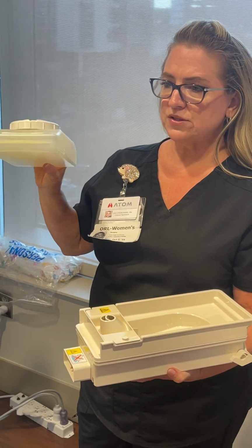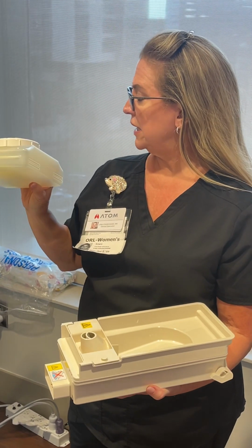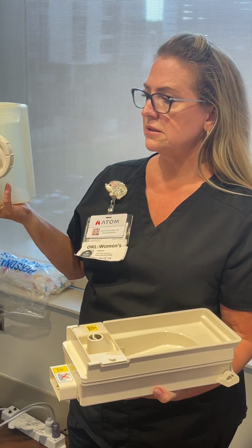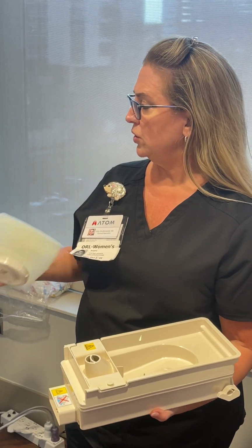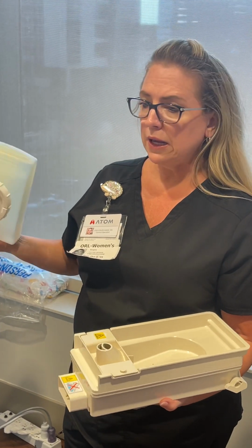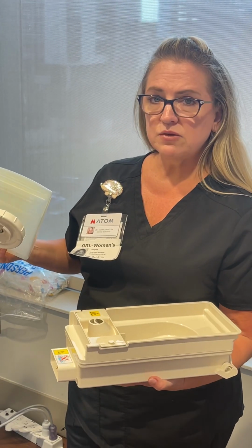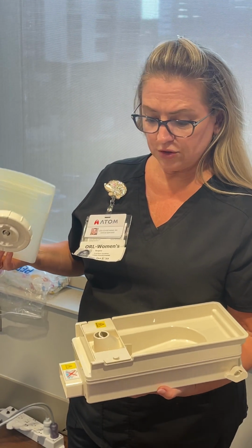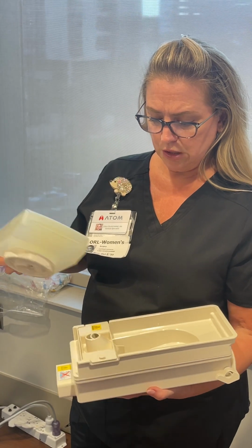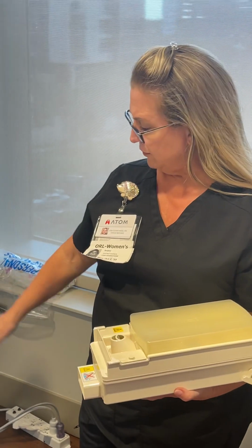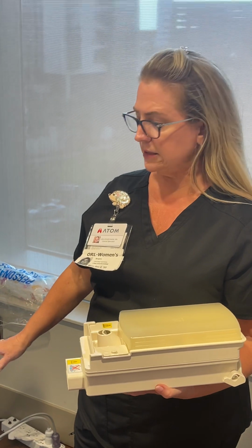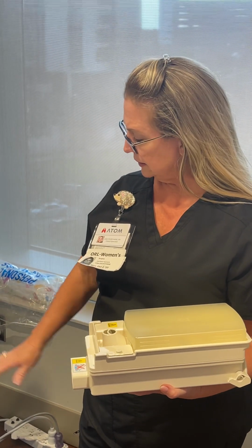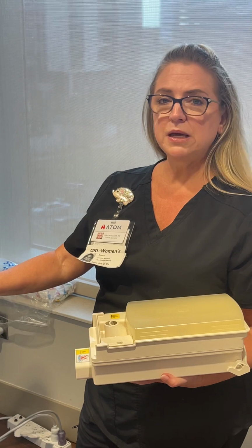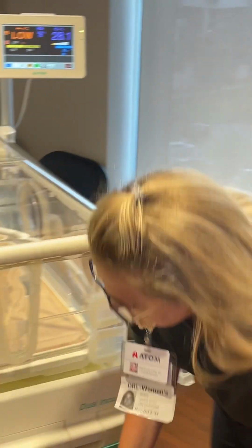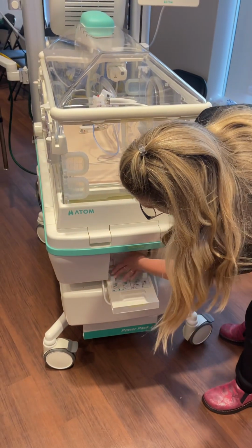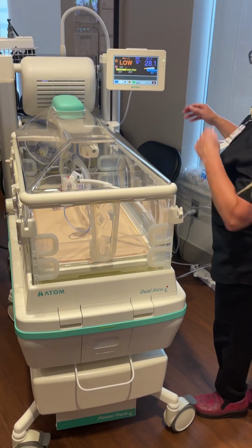There's a white paper study where we purposefully contaminated the tank with Pseudomonas and staph, then ran it through the unit repeatedly, and nothing cultured out. So as an infection control standard, this is superior to what you're used to. We don't have tubing or baffles that can't be removed or cleaned. Everything can be physically inspected and cleaned, even with a baby in the unit, in 3 to 5 minutes. It just loads back in and the door shuts.